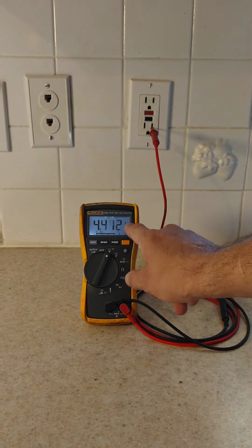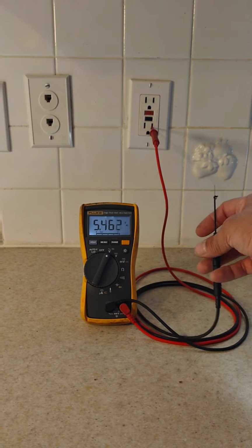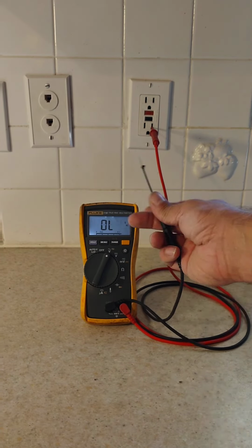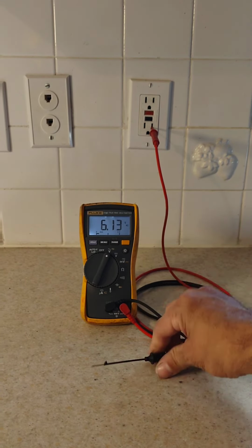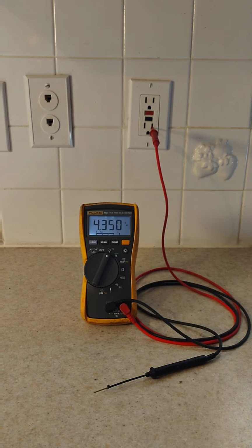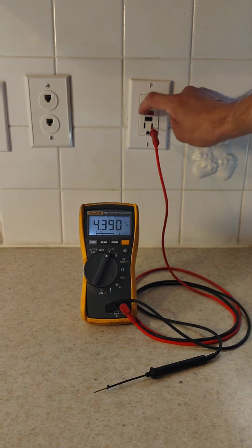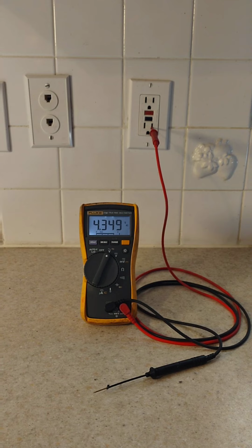So anytime you see this condition where your meter is showing voltage that changes as you move or touch your probe, that should be a really good clue that you have an open neutral somewhere. And you'll need to find that to find the problem. So what did that tell us? Well, it told us a couple of things: that we had a break in the circuit, that it was somewhere upstream from us.